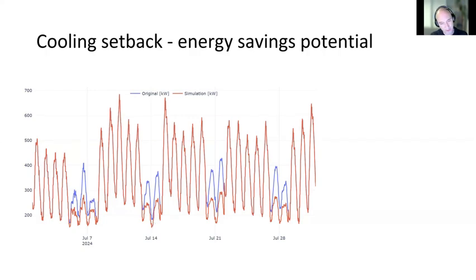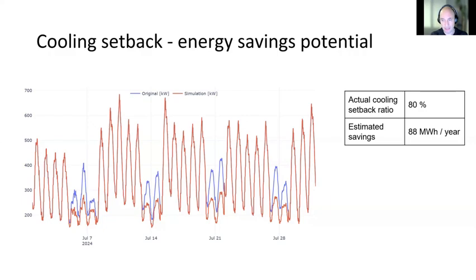That's the simulation, indicating how it will look if we are able to reduce the cooling setback from 80 to 30%. You may see there is still a significant portion of energy related to this time-dependent load. But since we are able to decompose it into time-dependent and weather-dependent, we may play around with this weather-dependent part and have this quite specific simulation, with numbers like: actual cooling setback ratio is 80%, and estimated savings in this particular building are 88 megawatt hours per year. This provides us this whole-year simulation.